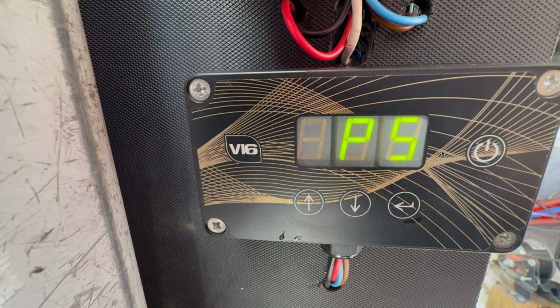So we've talked about the dead end, set too high and set too low. So basically, the dead end is an electrical switch off of your pump. Yeah. So now we'll go on to PS or P5, which is pressure switch. And this is a mechanical stop, isn't it? It's a mechanical stop on the pump and an electrical stop on the controller. Again, what we're looking at is when your pump pressure switch opens, so we've got too much pressure and the pump stops to protect itself, it's actually a mechanical switch, and it physically opens and stops the pump. Now, when that happens, there's no electrical circuit.